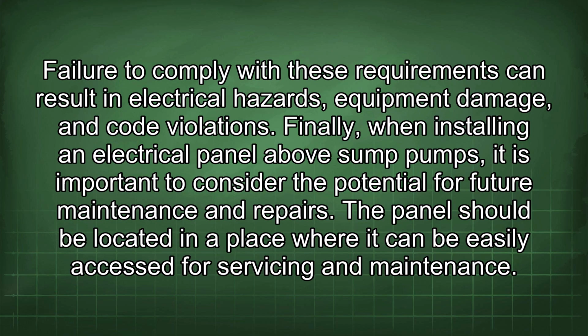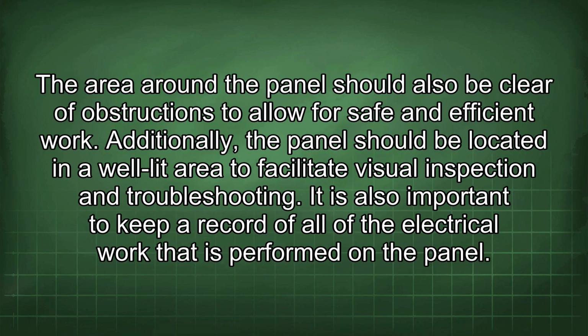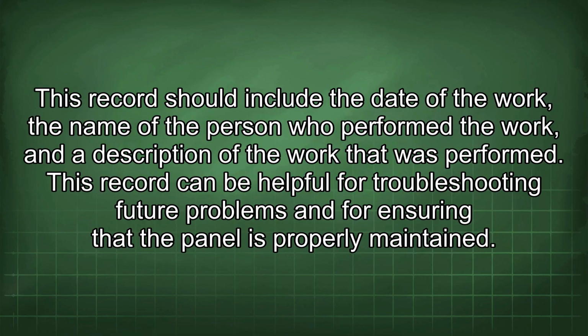Finally, when installing an electrical panel above sump pumps, it is important to consider the potential for future maintenance and repairs. The panel should be located in a place where it can be easily accessed for servicing and maintenance. The area around the panel should also be clear of obstructions to allow for safe and efficient work. Additionally, the panel should be located in a well-lit area to facilitate visual inspection and troubleshooting. It is also important to keep a record of all of the electrical work that is performed on the panel. This record should include the date of the work, the name of the person who performed the work, and the description of the work that was performed. This record can be helpful for troubleshooting future problems and for ensuring that the panel is properly maintained.